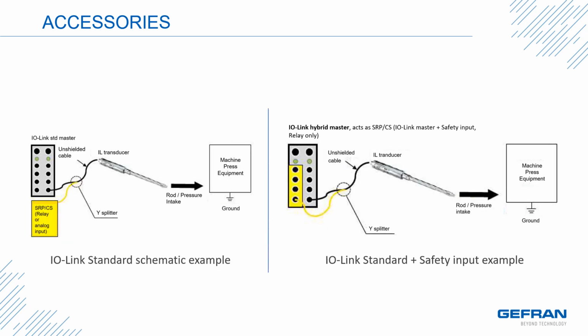The graphic here shows two simple examples of a Gefran IO-Link melt pressure sensor connected to an IO-Link master. On the left is a standard example. And if your sensor is configured with a safety output, either relay or auxiliary analog output, you could use a Y cable to be able to route that safety signal to its intended location. On the right is an IO-Link master that has a designated safety input block, and therefore you could use a cable splitter type to route that safety signal to the dedicated port on that IO master. And then it would be further routed to where it needs to go in the system.